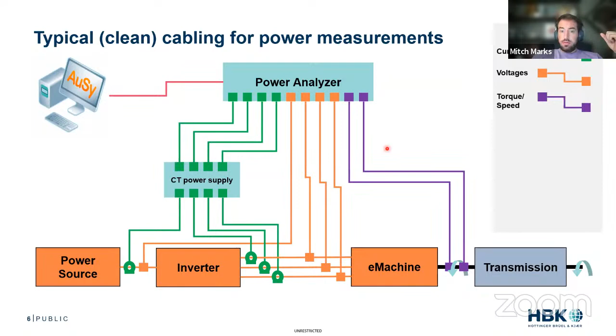So what does this look like in reality? I know none of your labs have ever looked like this, but here's a picture from a customer of mine where an inverter is connected to a power analyzer — I think this was a 6-phase system. So there's tons of cabling: torque and speed lines, coils of wire, things stacked on one another. It's a nightmare — thermocouple measurements, controllers just hanging out. This is a safety issue, and it's also an EMC issue.